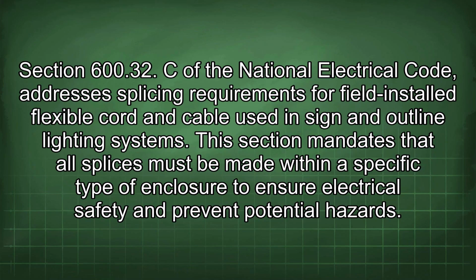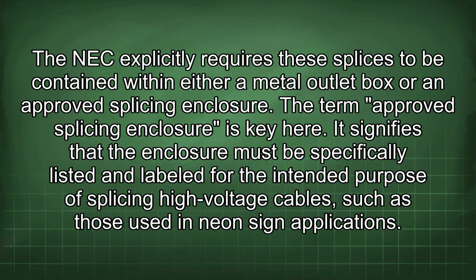Section 600.32 C of the National Electrical Code addresses splicing requirements for field-installed flexible cord and cable used in sign and outline lighting systems. This section mandates that all splices must be made within a specific type of enclosure to ensure electrical safety and prevent potential hazards. The NEC explicitly requires these splices to be contained within either a metal outlet box or an approved splicing enclosure. The term approved splicing enclosure is key here.